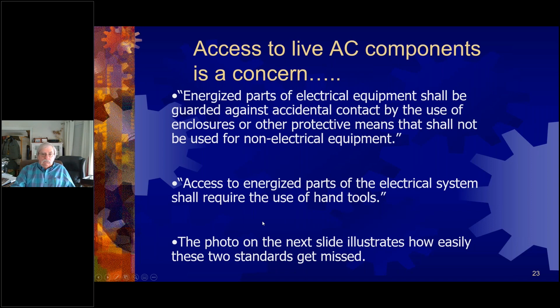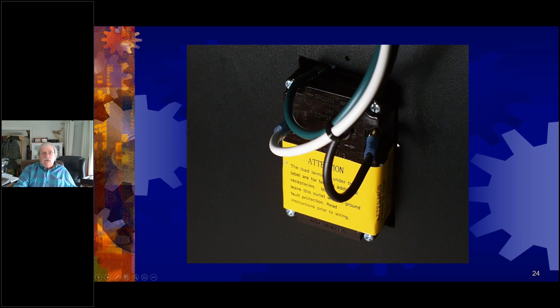Here's an example from a boat builder. This is a brand new boat, and the backside of that AC receptacle was inside a locker in the main salon area where people are going to be throwing all manner of equipment. These are live AC terminals, unprotected. It's not a question of if, but when we get an arc fault because a stray beer can happens to rub up against these hot wires. It's potentially dangerous.